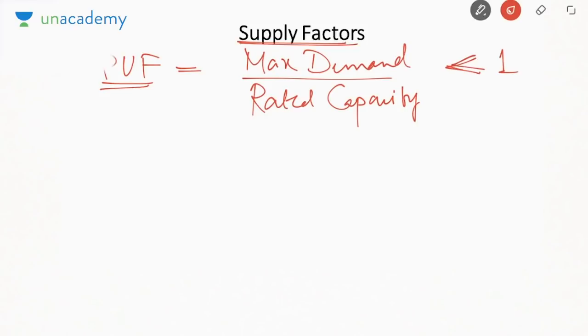Now suppose the capacity is 200 megawatt but the demand is 50 only. That means you are wasting 150 megawatts capacity of the plant. It can generate 150 megawatt more, but you are not using that additional capacity. So this factor should be as close to 1 as possible so that we are efficiently utilizing the plant. Next is called plant capacity factor or even plant factor.